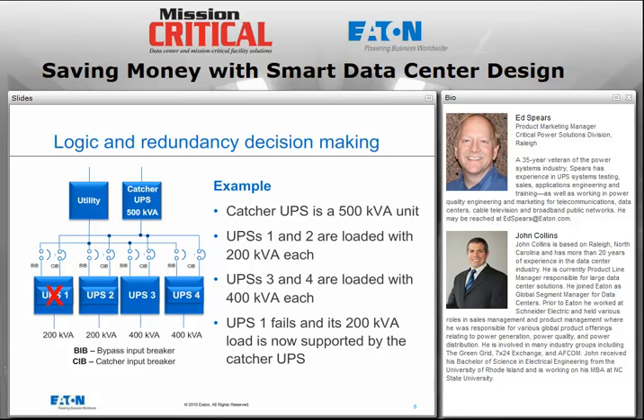So what happens if we suffer a failure on UPS 1? Well, clearly, if that happens, UPS 1 will transfer to its bypass via its static switch and will begin to draw energy from the catcher system. Now, normally in a traditional system, at this point, the catcher system is basically taken away from the rest of the primary UPSs. It's now dedicated to supporting the one failed UPS. But in this particular case, you can see that I have 300 kVA of capacity left over in my catcher system. It would be really nice for the system to be smart enough to know that if UPS 2 were to subsequently fail, I could still handle that with the catcher.